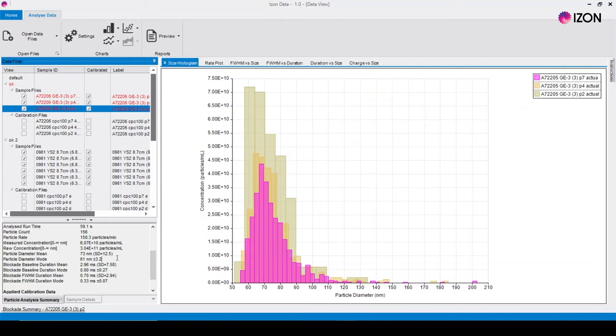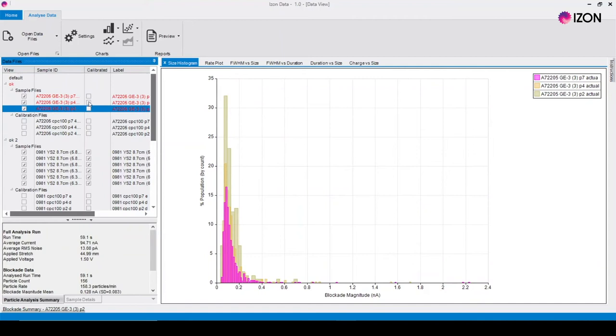If you need to change the calibration a sample uses untick the box next to the sample in the calibrated column then click the box again to return to the calibration menu.